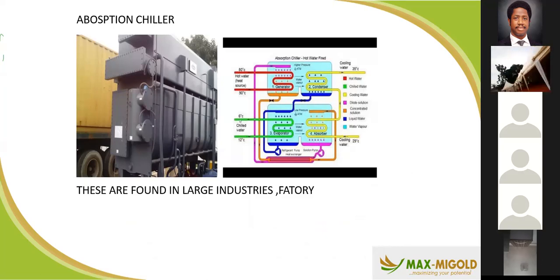That is Mandela's. Back then, they bought about two, and they have high expenses — this should be between 90 to 100 million. They needed it for their building because they're actually going on automation, and the automation requires a lot of engines working together at the same time. So these equipments were brought in to work. They use a refrigerant called lithium bromide. They use the excess heat coming in from your generator to do the separation and bring the required cooling to all their facility and equipment.